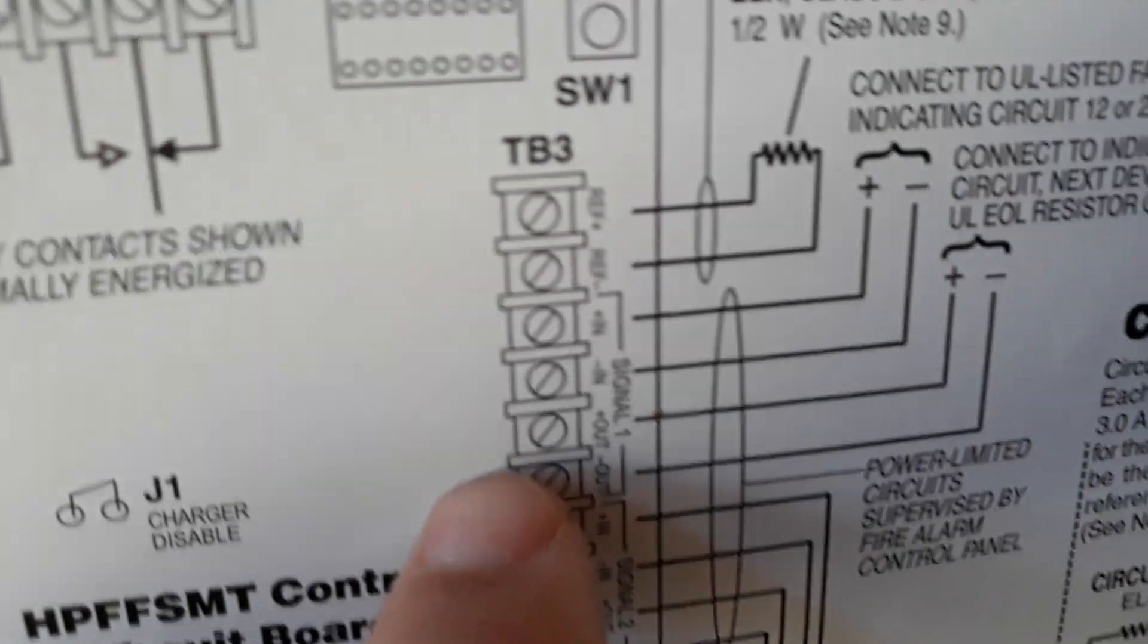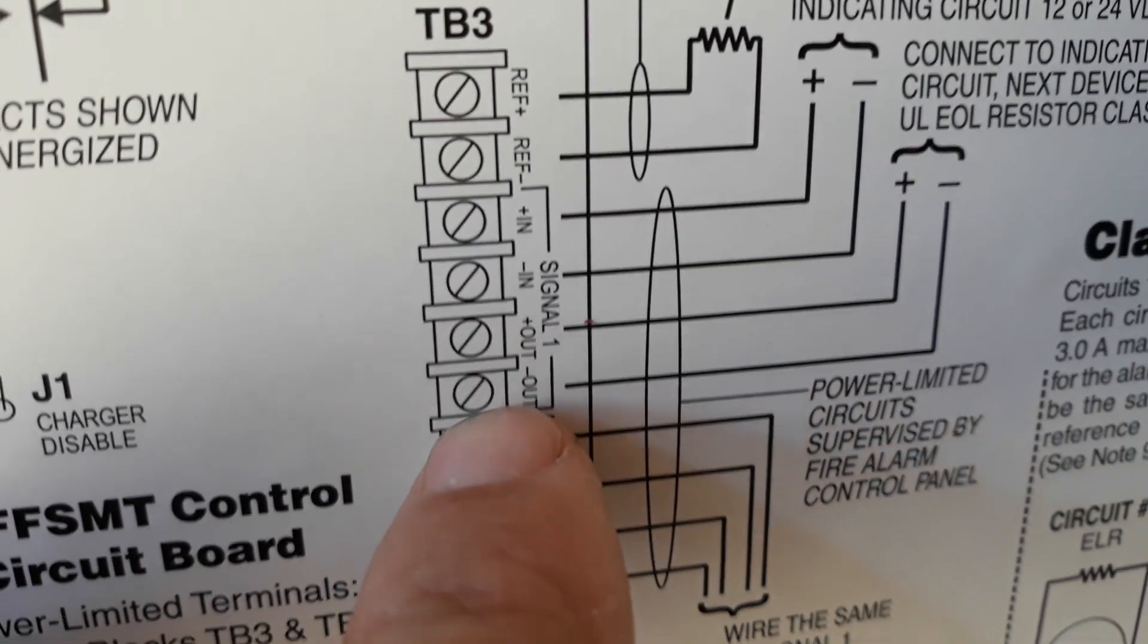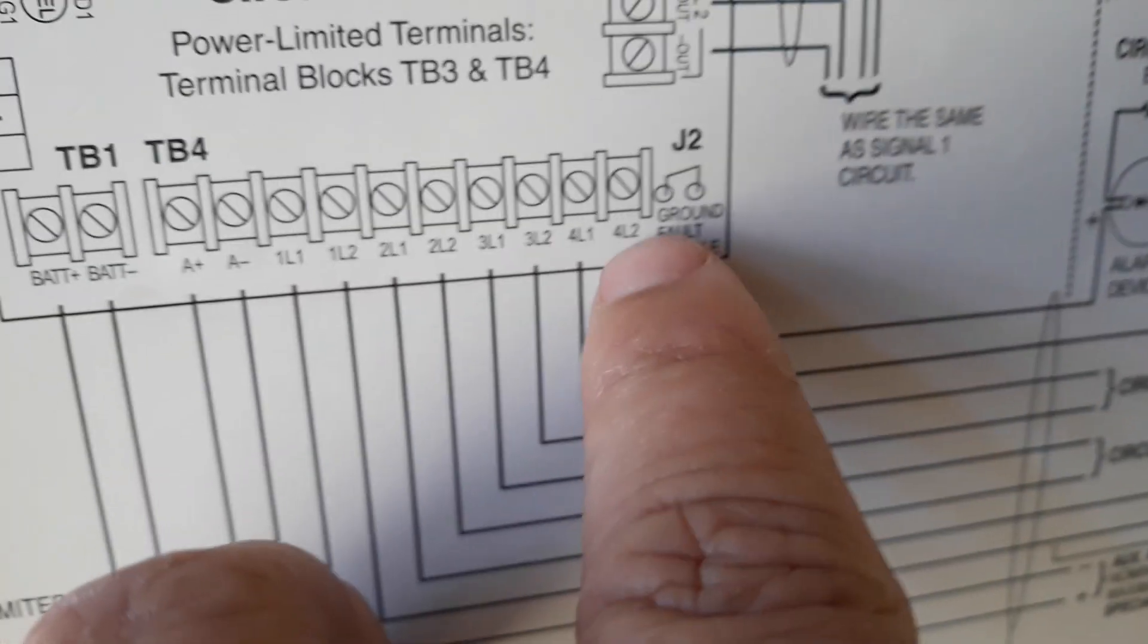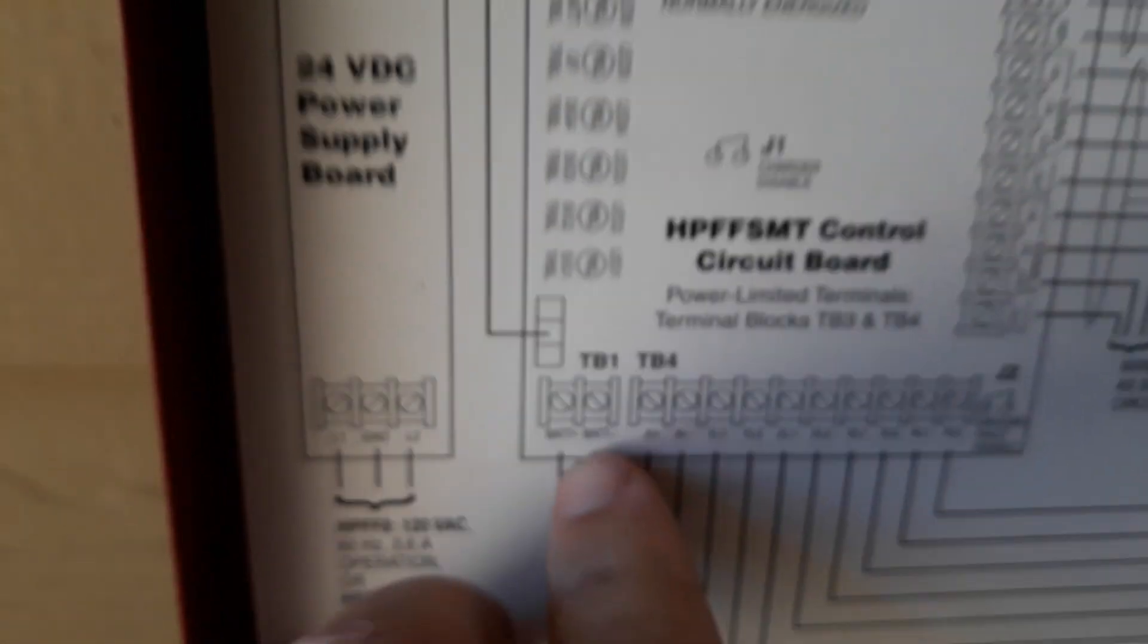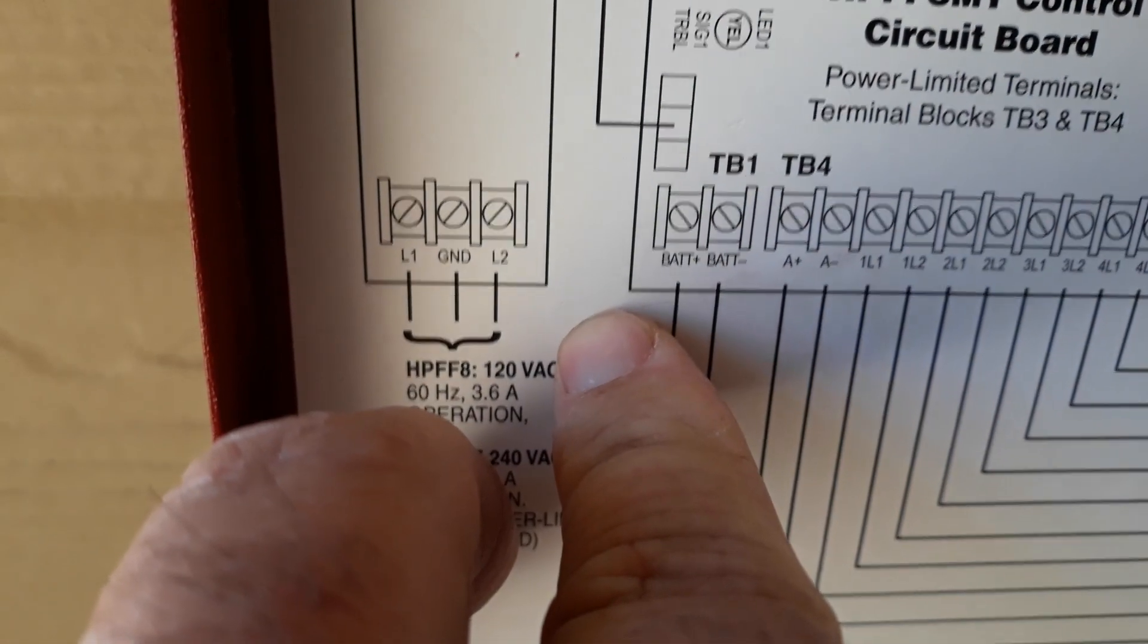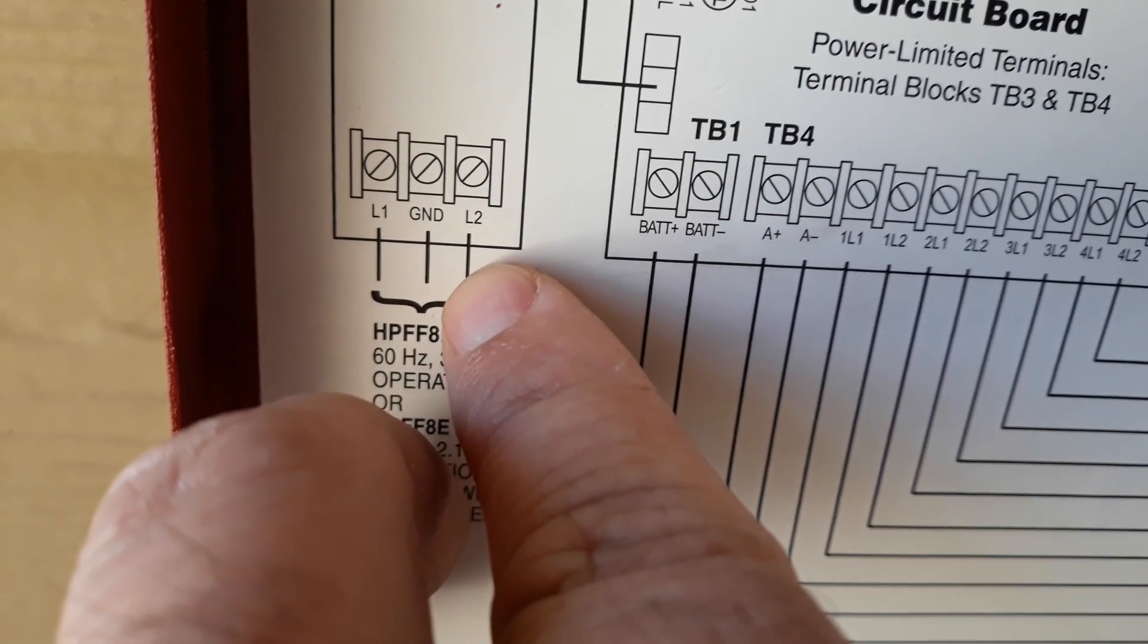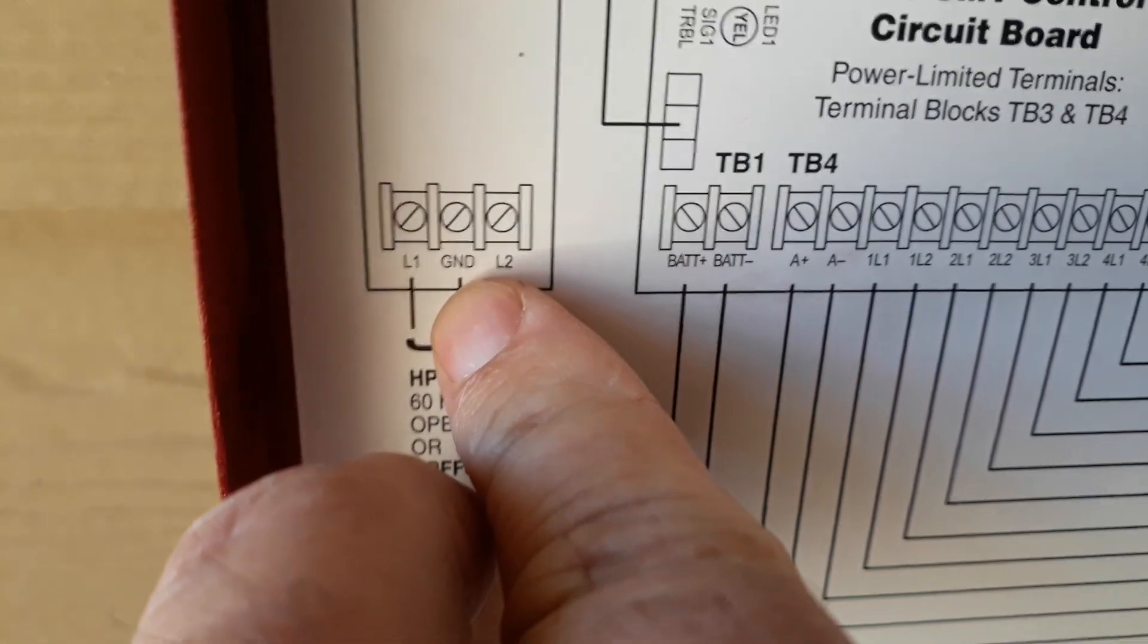So up here on the signals, inputs and outputs, they put the plus and minus for the field wiring and they didn't. So it gives you the option for ground fault disabled. I highly recommend never doing that. And also another thing too. See right here, L1, ground and L2. How hard would it have been to say hot, ground and negative? A lot of guys in the field aren't electricians. They don't know what L1 and L2 does.